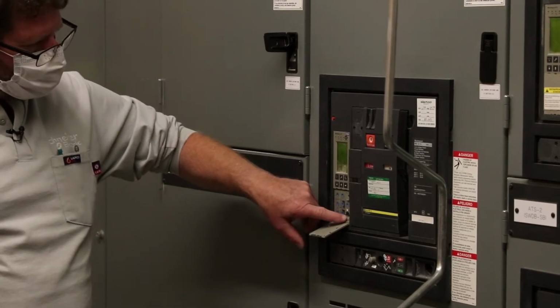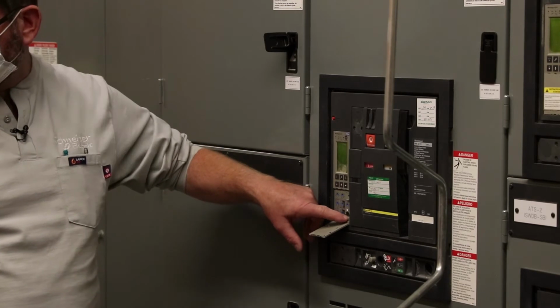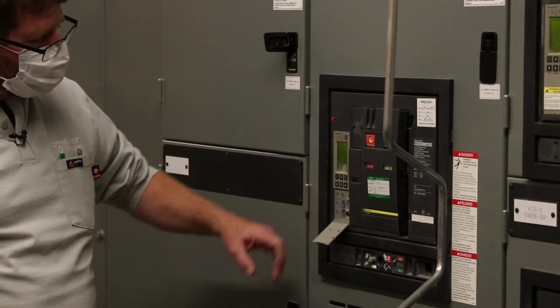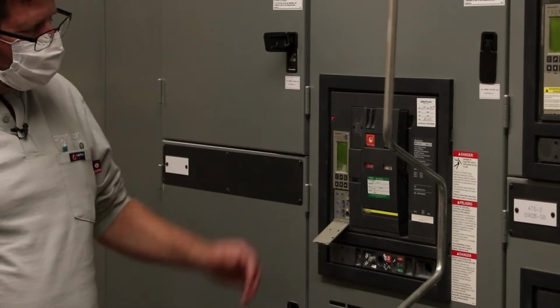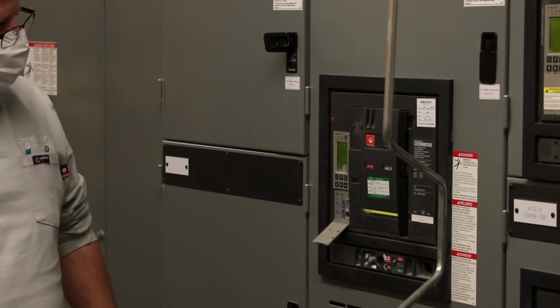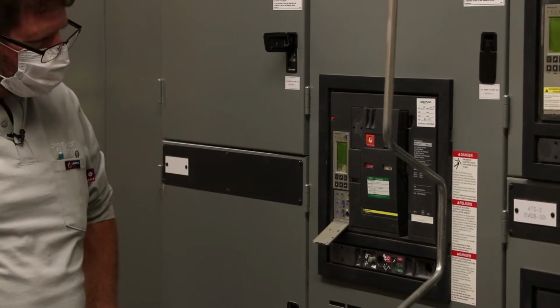The other thing here you have is a port that's for testing the breaker. There's a test set, a couple different test sets available. You can plug in there, simulate load into the breaker, and have the breaker trip off on its protective functions.